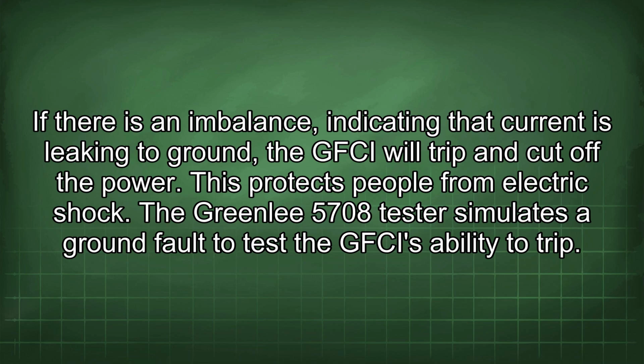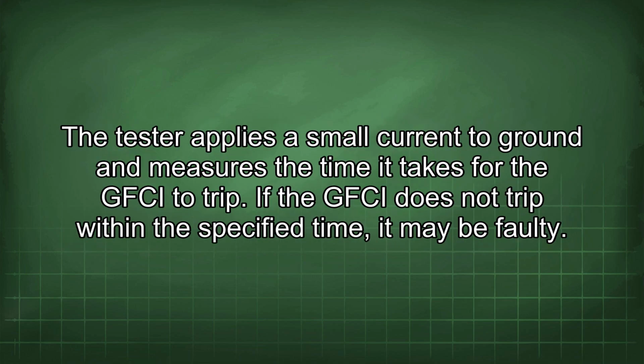The Greenlee 5708 tester simulates a ground fault to test the GFCI's ability to trip. The tester applies a small current to ground and measures the time it takes for the GFCI to trip. If the GFCI does not trip within the specified time, it may be faulty.